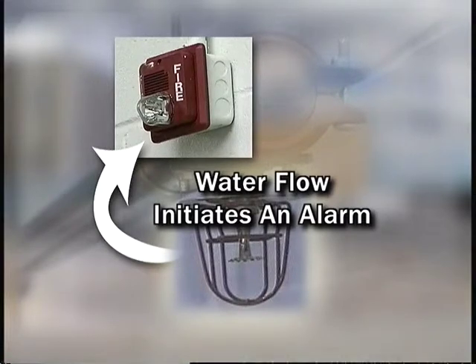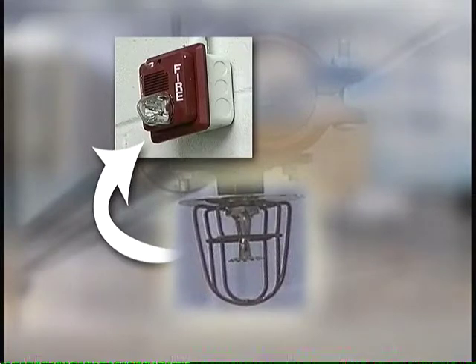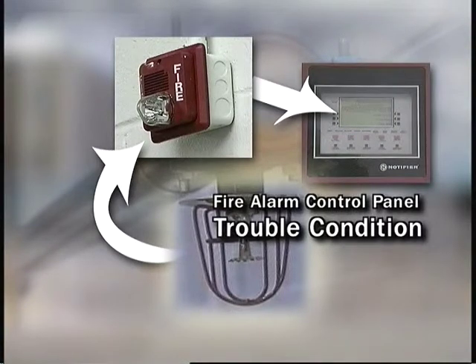The main sprinkler system and riser valves are provided with automatic monitoring of pressure, tamper, and flow status at the zone valve assembly. If the tamper switch at any system component is activated, or if the low water pressure switch is activated, this signal will cause a trouble condition on the fire alarm control panel, and its identification will be annunciated.